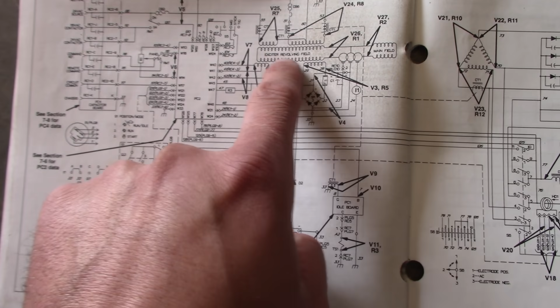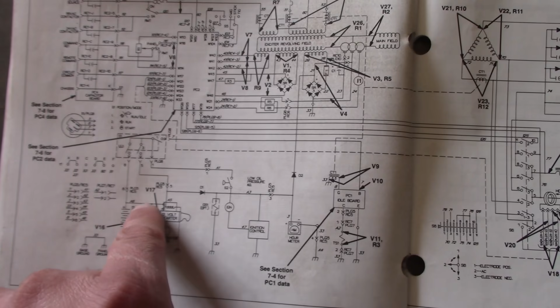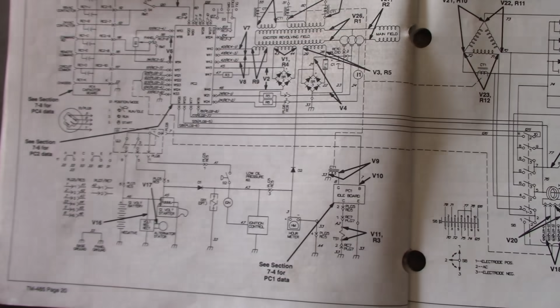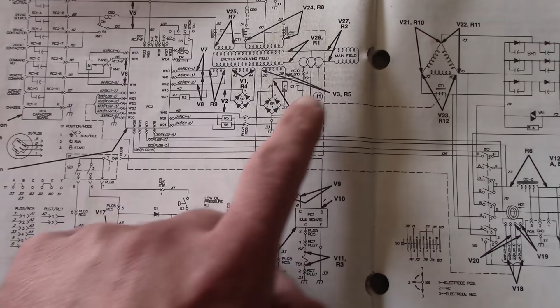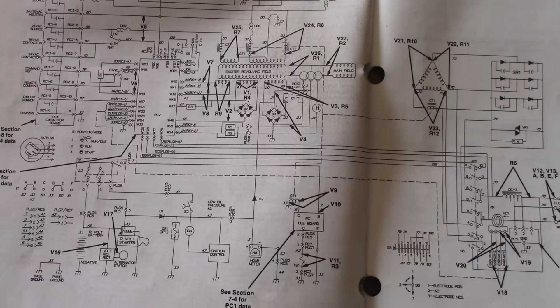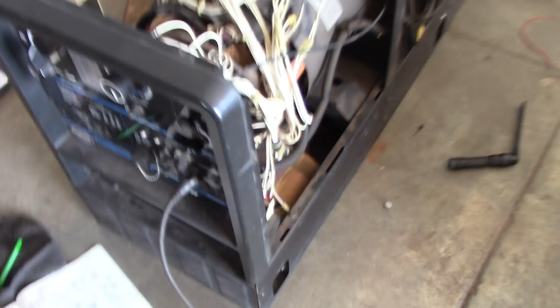What I think is happening is this circuit isn't really doing anything. The only voltage making it into the exciter field is the 12 to 14 volts coming from the battery slash the engine alternator through these diodes. So this section doesn't seem to be working at all. I checked between 28 and 29, across the winding here, it's less than 1 ohm and not shorted to ground, so I don't know what's going on. The fuse is also good. Anyway, put that back together and we'll see what happens.